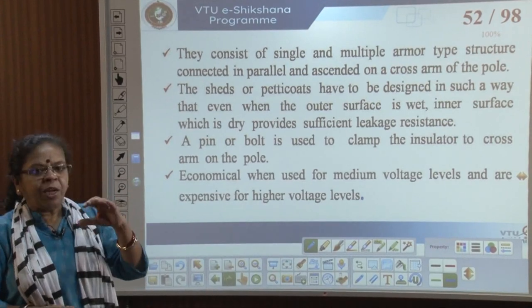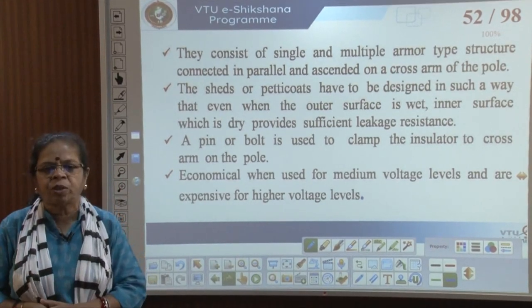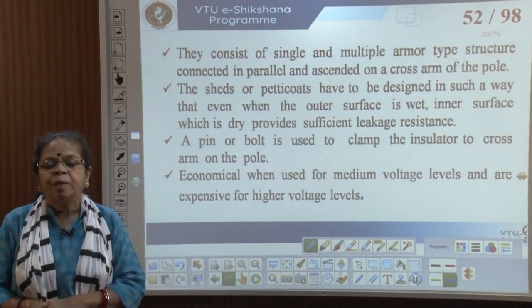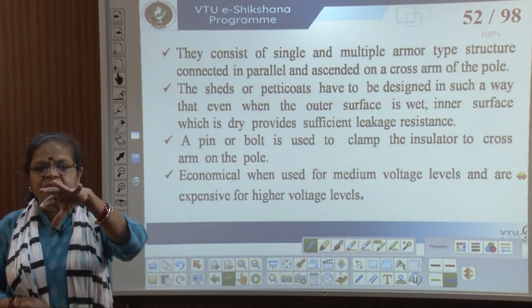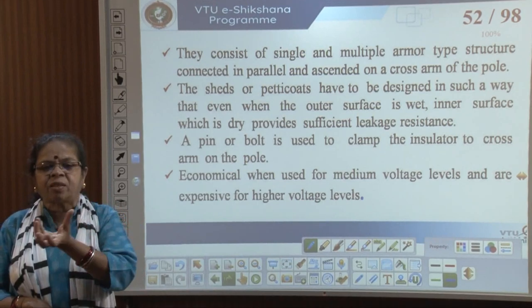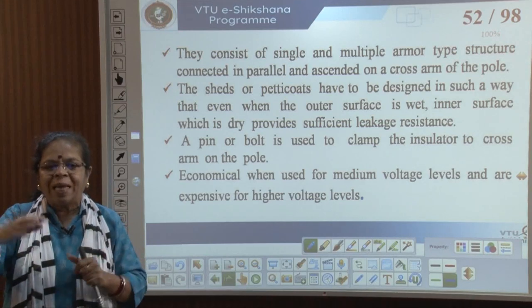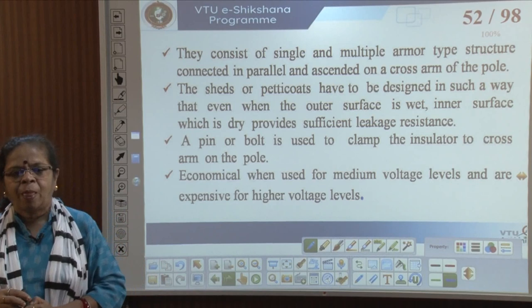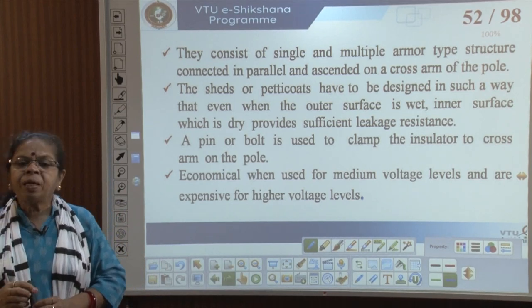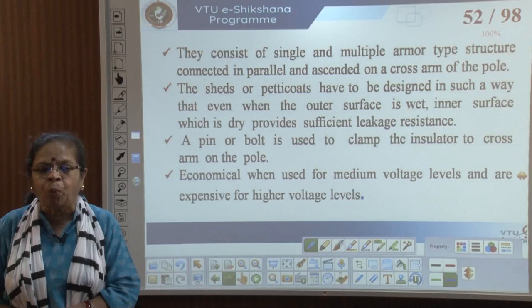The sheds or petticoats are designed so that even when the outer surface is wet, the inner surface is dry — water falls off and tapers off like sloping roofs. A pin or bolt is used to clamp the insulator to the cross arm on the pole, and it is used for medium voltage levels; for high voltage it becomes expensive.